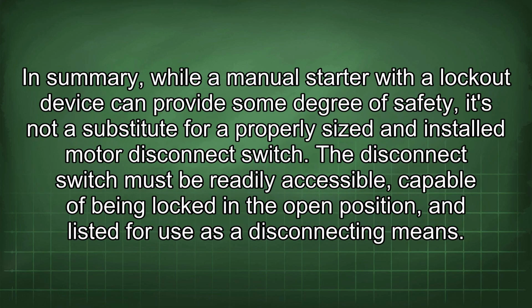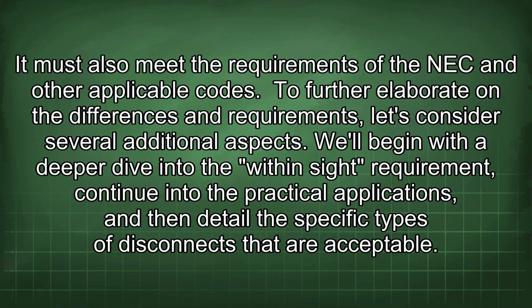contact. In summary, while a manual starter with a lockout device can provide some degree of safety, it's not a substitute for a properly sized and installed motor disconnect switch. The disconnect switch must be readily accessible, capable of being locked in the open position, and listed for use as a disconnecting means. It must also meet the requirements of the NEC and other applicable codes.